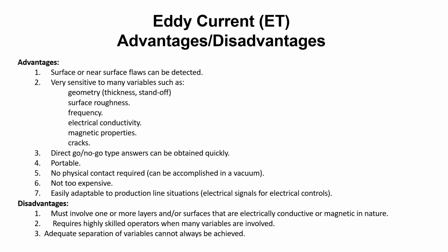Eddy current testing advantages and disadvantages. Advantages: surface or near surface flaws can be detected. Very sensitive to many variables such as geometry, surface roughness, frequency, electrical conductivity, magnetic properties, and cracks. Direct go, no-go type answers can be obtained quickly. It's portable, no physical contact required, can be accomplished in a vacuum, not too expensive, easily adaptable to production line situations. Electrical signals for electrical controls. Disadvantages: must involve one or more layers and/or surfaces that are electrically conductive or magnetic in nature. Requires highly skilled operators when many variables are involved, and adequate separation of variables cannot always be achieved.